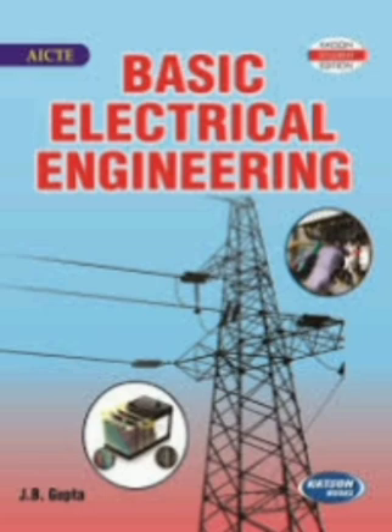Comparison between two winding transformer and auto transformer. Copper weight, Cu weight auto equal to 1 minus 1 by A auto, into copper weight of the two winding transformer. Copper saving, percentage copper saving equal to 1 by A auto into 100. KVA rating of auto transformer, KVA auto equal to A auto by (A auto minus 1), where A auto minus 1 is the denominator, into KVA two WDG, all multiplied. KVA auto equal to KVA rating of auto transformer. KVA two WDG means KVA rating of two winding transformer.